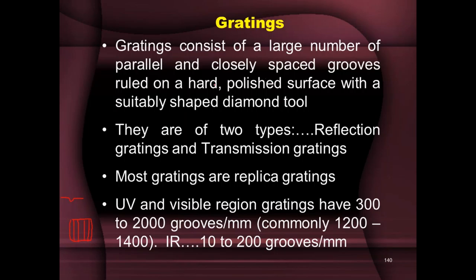This polished surface is for one type of grating called the reflective grating. If it is a transmission grating, the surface is transparent rather than polished. So gratings are of two types: reflection gratings and transmission gratings. Most gratings used in instruments are replica gratings because master gratings are very expensive. The cost of the instrument would go up drastically. So to avoid that, replica gratings — duplications of the master grating — are used.